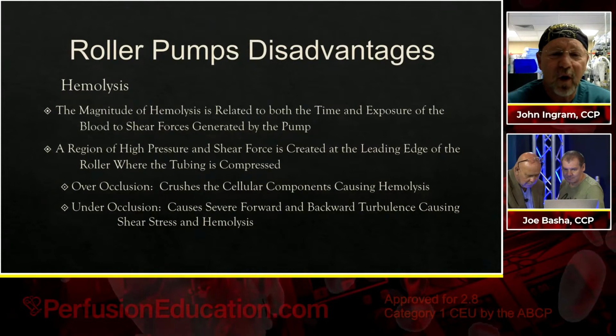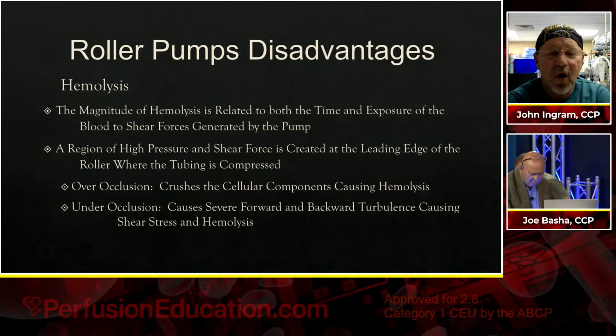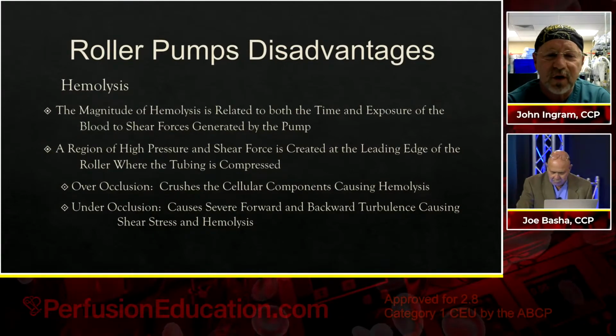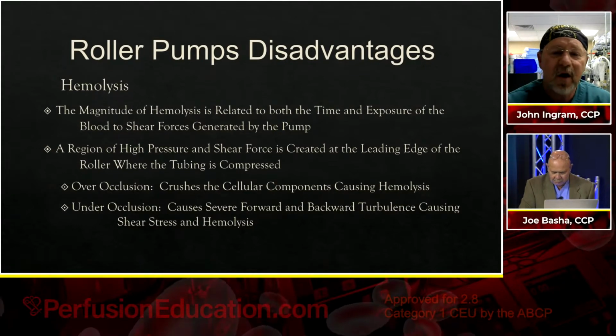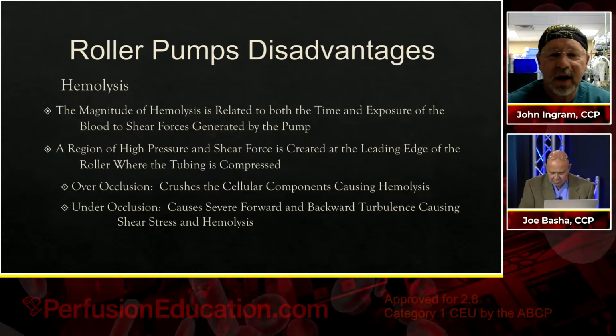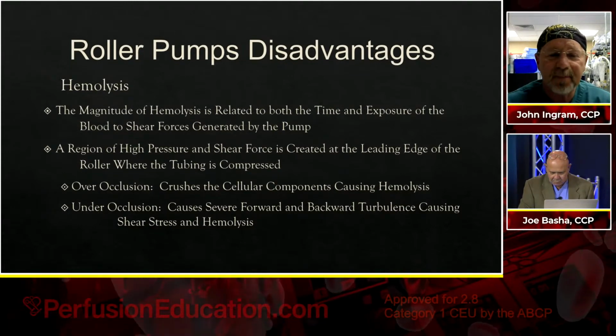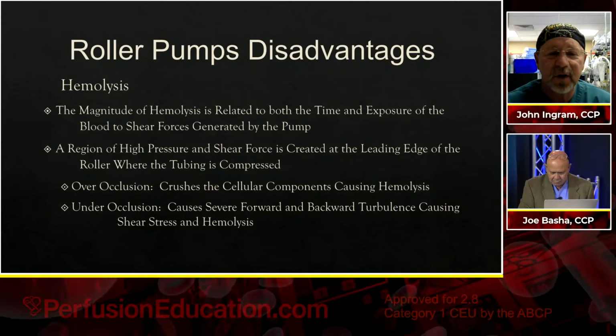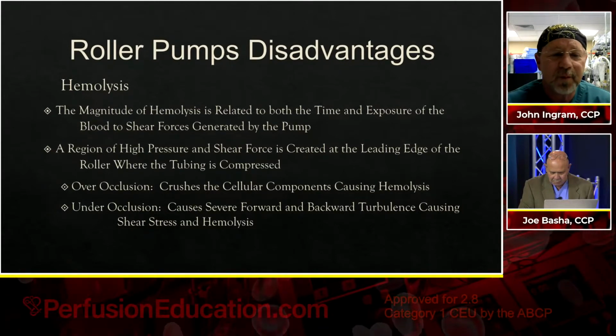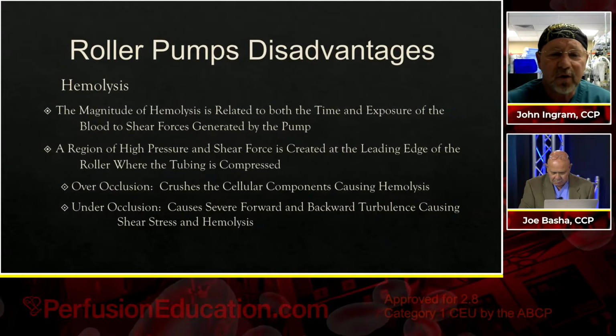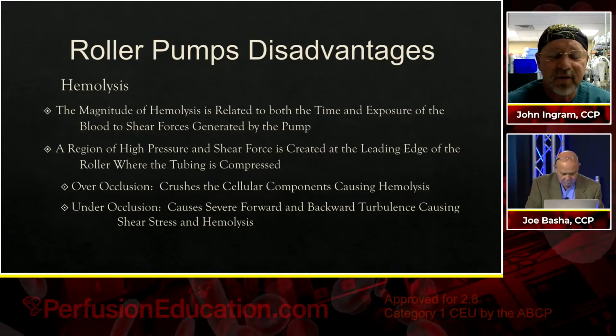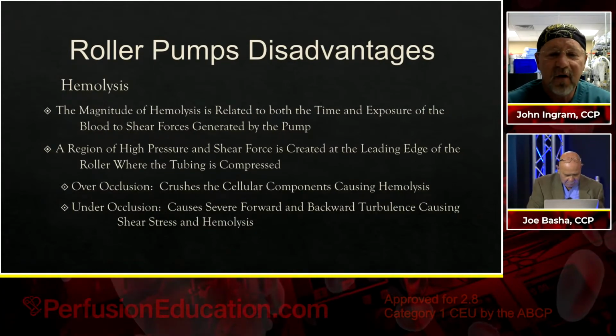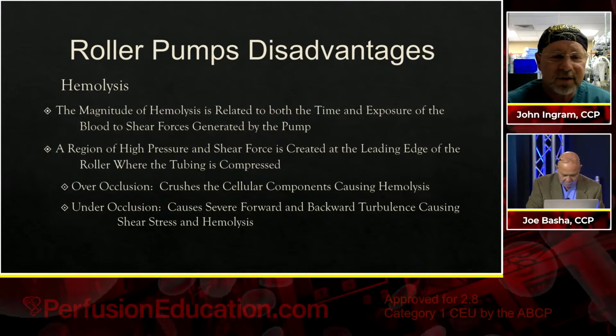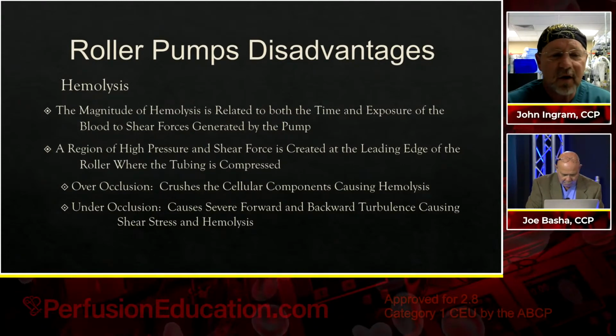This is why you don't want a 100% occluded roller pump, and why I showed you those occlusion techniques that allow for the ever so slight gap so that it's not completely occluded against itself when the roller comes by. There could be an under-occlusion. If it's under-occluded severely enough, you can have severe forward and backward turbulence causing shear stress and also hemolysis.